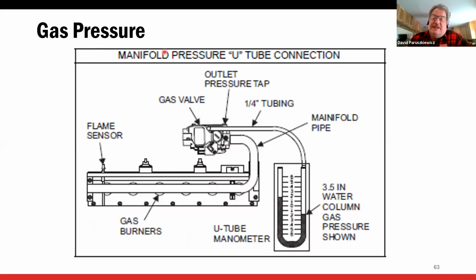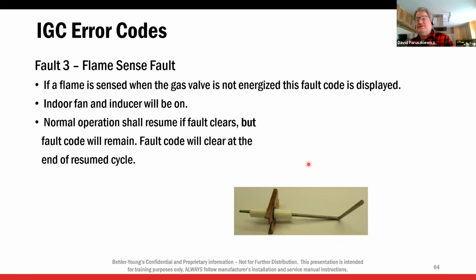Okay, gas pressure. This is another one I hear a lot of guys say: well, when that gas valve left the factory, they adjusted it to 3.5 inches, blah, blah, blah. Yeah, they might have. But again, this unit has traveled thousands of miles. The freight company handled it. We handled it. That gas pressure is not in line anymore. And I've seen these things right out of the box with 3.8 gas pressure because those need to be adjusted. You put your manometer on there, you adjust it to the rating plate. That is something that has to be done. Overfired is going to cause high temp rises and limit trips. So again, limit trips are caused by airflow issues, stratification, or high gas pressure, overfiring.